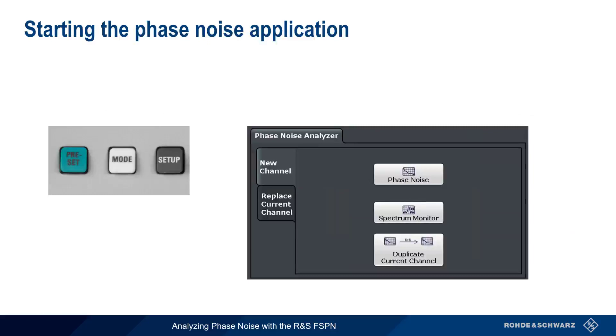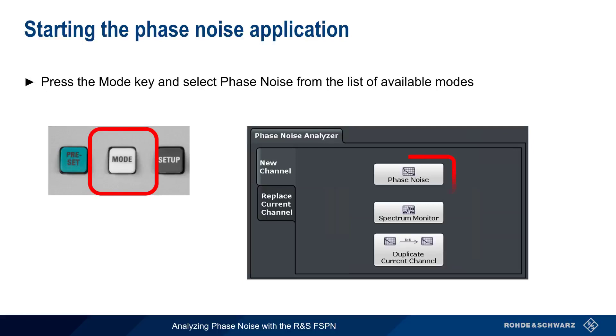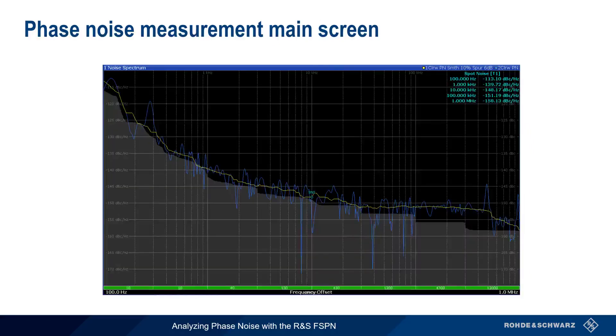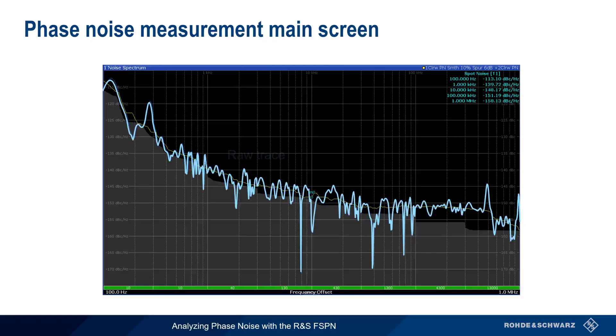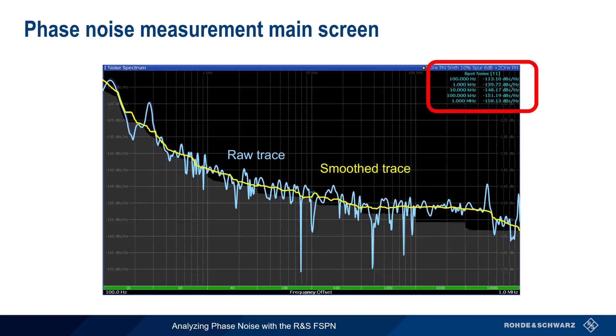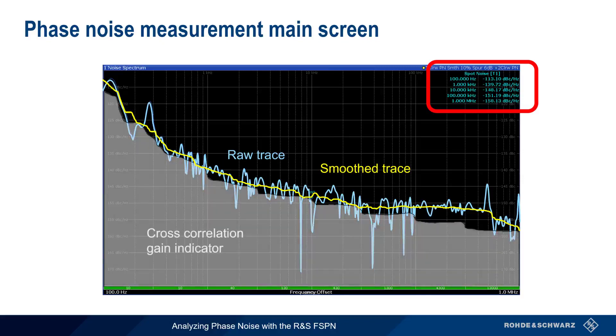To start the phase noise application on the FSPN, simply press the Mode key and then select Phase Noise from the list of available modes. This is the main phase noise measurement screen. In most cases, the source signal will be automatically detected and measured by the FSPN. By default, phase noise results are usually given as both raw and smooth traces of the single sideband phase noise. Phase noise is also shown as numeric values or spot noise, and if cross-correlation is used, the gray area beneath the trace shows the cross-correlation gain. In the remainder of this presentation, we'll explain how to modify default values and behavior, and how to use additional features and functionality to make and interpret phase noise measurements.